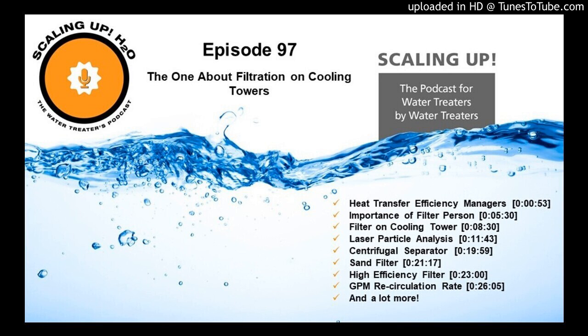And I will tell you, Bryan, we're dealing with pollen right now. We have a lot of centrifugal separators that were sold when the cooling tower was sold to the client, and they do nothing for pollen. So you are 100% right about that. Yeah. I hate to downplay anybody else's equipment, but the facts are it's 70 micron for centrifugal, 30 micron for single media filter, and 0.5 micron for high efficiency filter. So it's a dramatically different result.